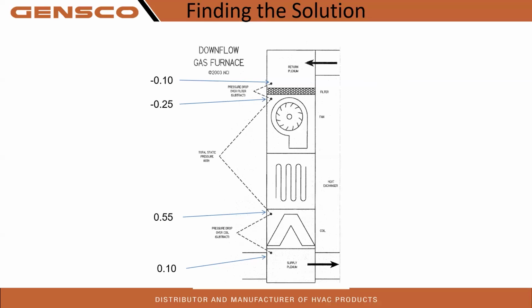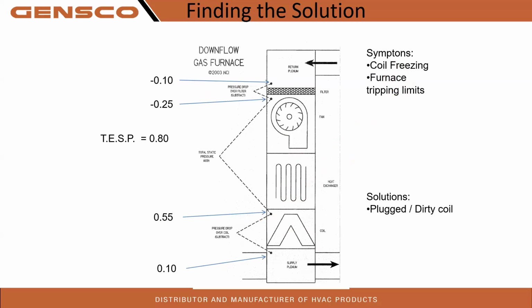Here's another one. We got a 0.1 on the return. We got a 0.25. So we got 0.15 across that filter. Ooh, look at that, 0.55 on that evaporator coil. Let's see. So we got a total external static pressure of 0.8. Again, same symptoms. Our coil could be freezing, trapping air, and our furnace is tripping limits in E04. So we're overheating the heat exchanger. Why? We got another plugged, dirty coil possibly.